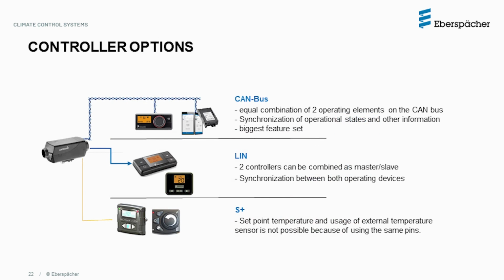Multiple controller types can be used simultaneously with one heater, or multiple heaters can be operated via a single CAN controller. A CAN-based Easy Start Pro controller would be the most preferred option in most applications. Synchronization between multiple CAN-based controllers is possible, and the heater or heaters in the application can be operated via either of the controllers. The 12-volt second-generation Airtronic 2 heaters with the most current version of the ECU software can also be operated with the LIN interface.